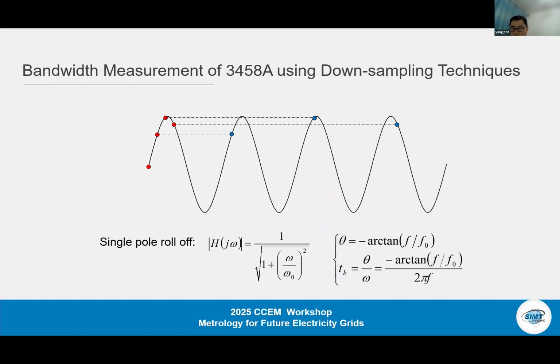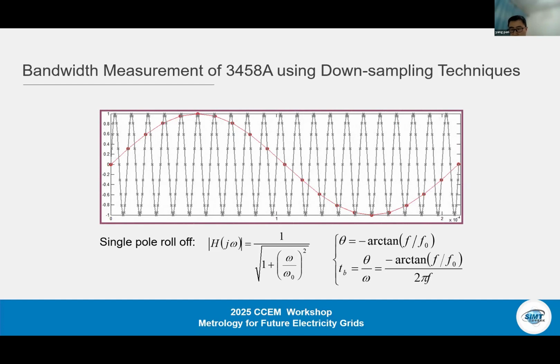According to the manual, the bandwidth varies from 30 kilohertz to 150 kilohertz, depending on the range selected. While this performance data is characteristic instead of a guaranteed specification, it needs to be measured in order to compensate accurately. However, direct bandwidth measurement at frequencies up to 150 kilohertz is not possible because the maximum sampling rate is limited to 100 K in DCV mode. So we use a downsampling technique, sampling in different periods and mapping samples to the corresponding instance within 1 period, and have successfully obtained the bandwidth, combined with the improved quasi-synchronous algorithm.